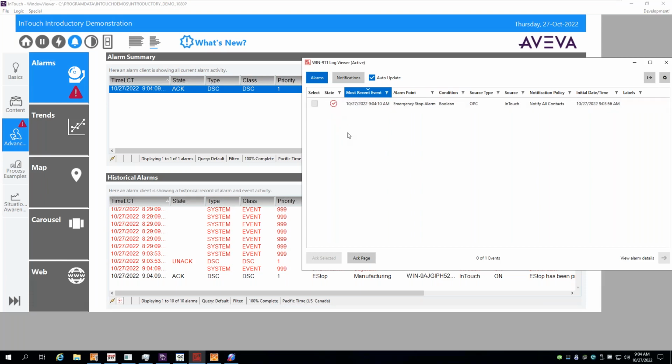And so you've created this direct connect functionality through OPC instead of using the normal InTouch Direct Connect. So I'm showing you InTouch. Maybe if you guys don't like the InTouch Direct Connect because of the SuiteLink issues, or if you're doing the terminal services versions of InTouch, it can sometimes be a hassle. You could replace that with an OPC configuration and do it this way instead. Yeah, okay, that's how that works.